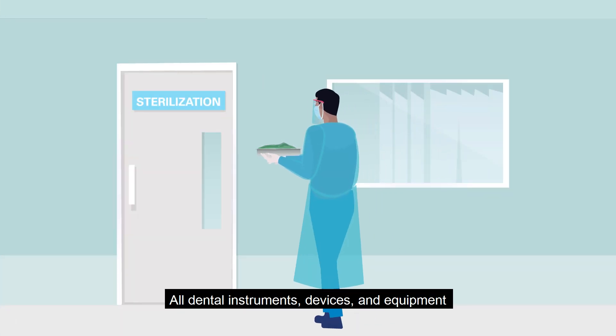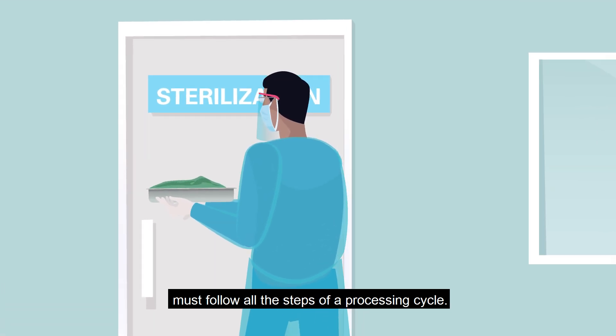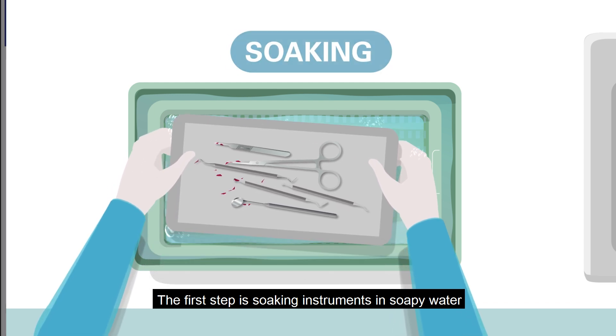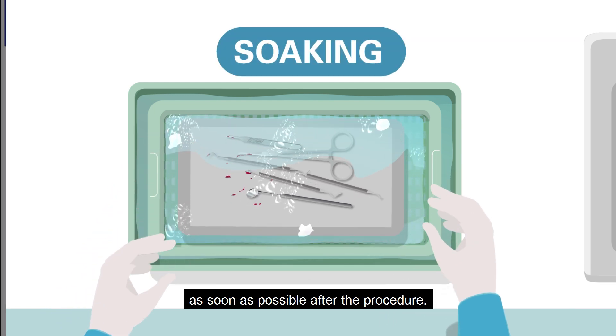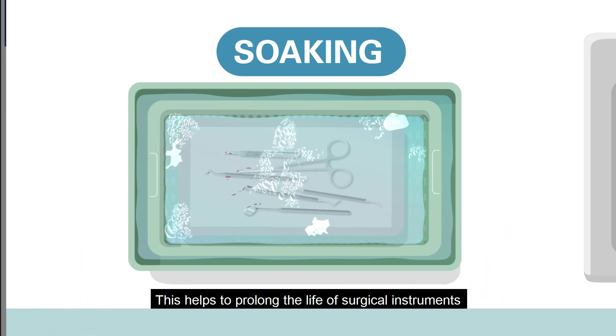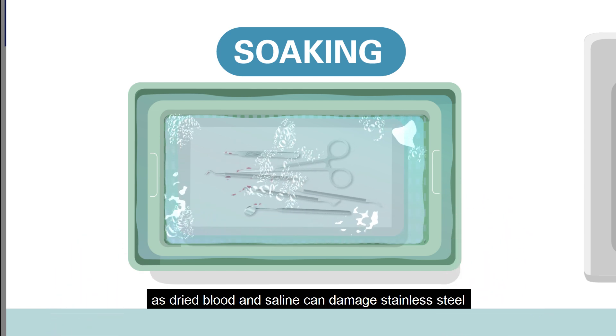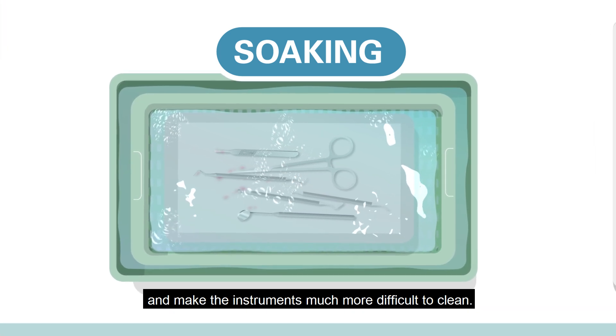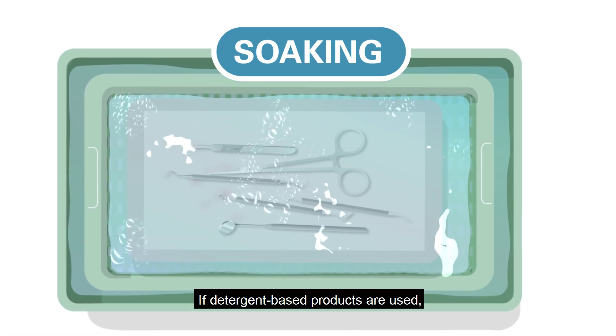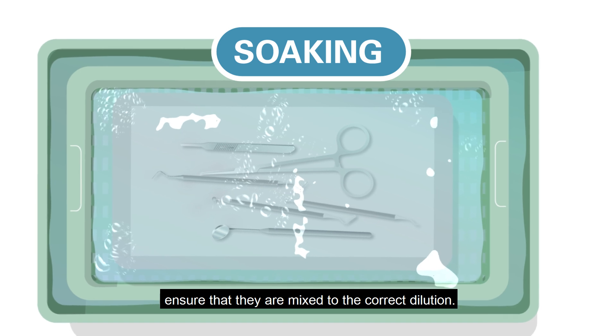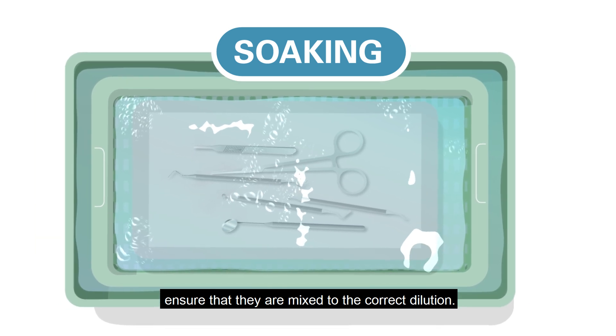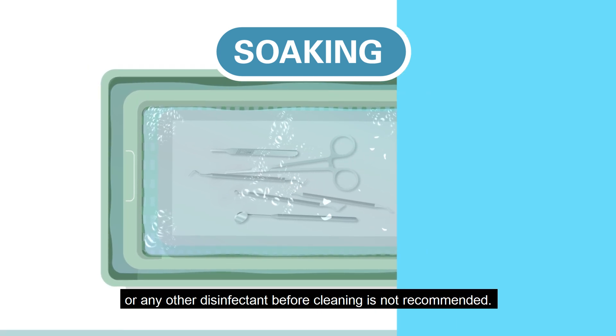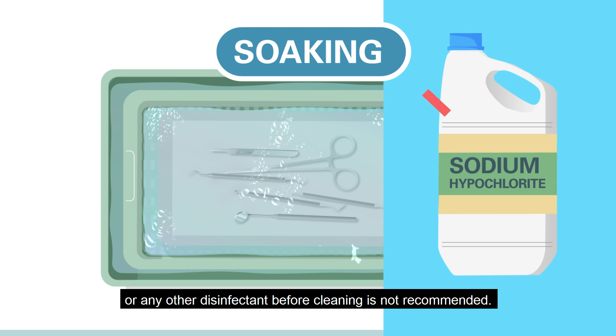All dental instruments, devices and equipment must follow all the steps of a processing cycle. The first step is soaking instruments in soapy water as soon as possible after the procedure. This helps to prolong the life of surgical instruments as dried blood and saline can damage stainless steel and make instruments much more difficult to clean. If detergent-based products are used, ensure they are mixed in the correct dilution. The soaking of instruments in 0.5% chlorine solution or any other disinfectant before cleaning is not recommended.